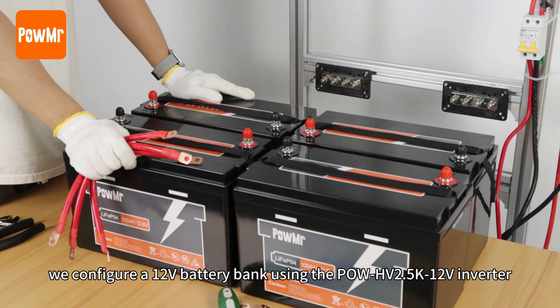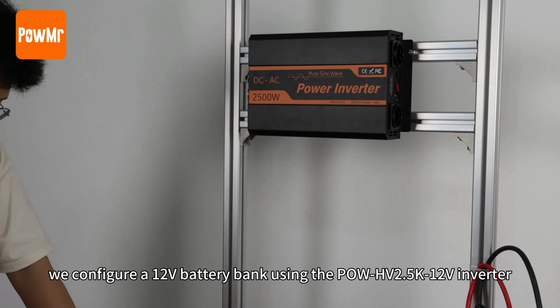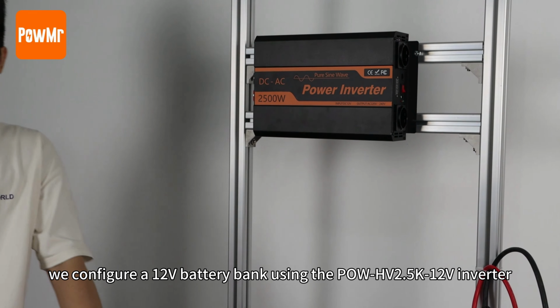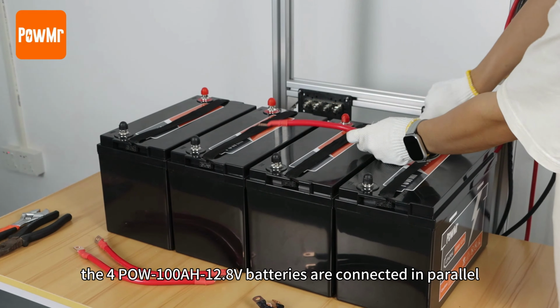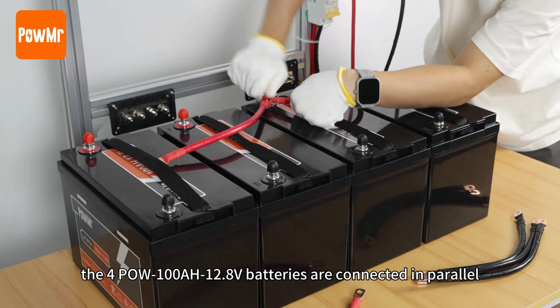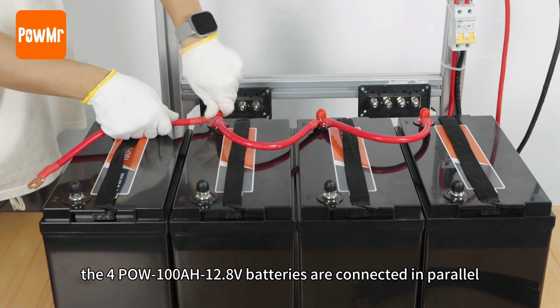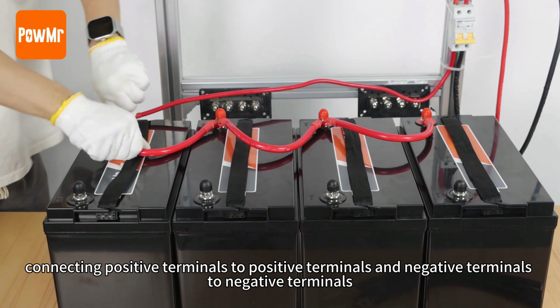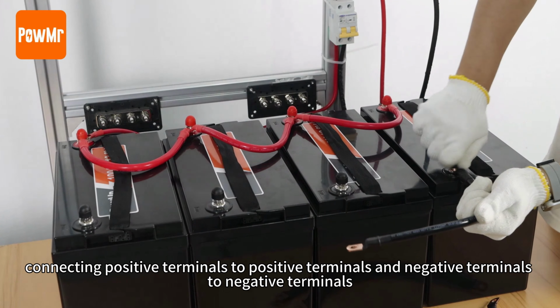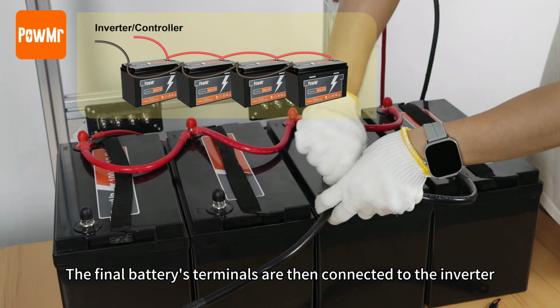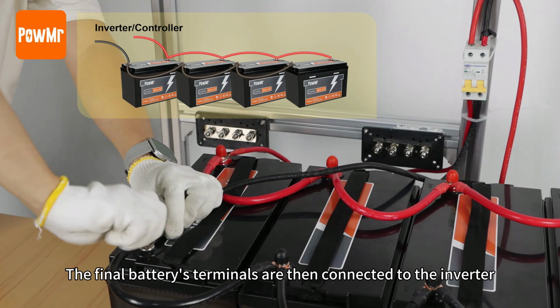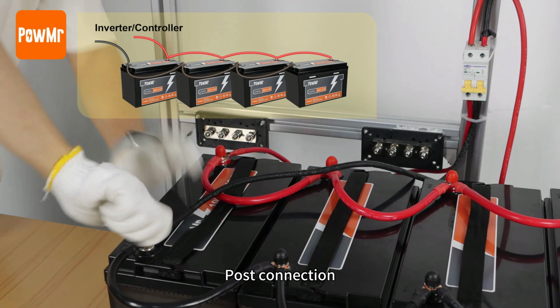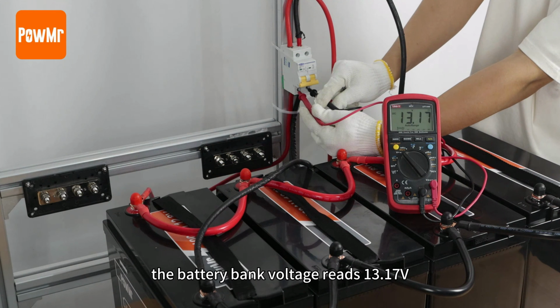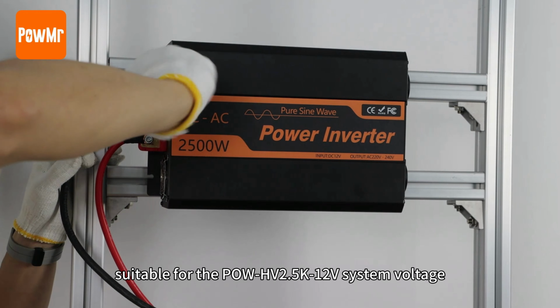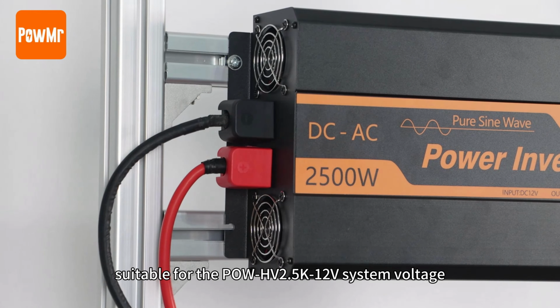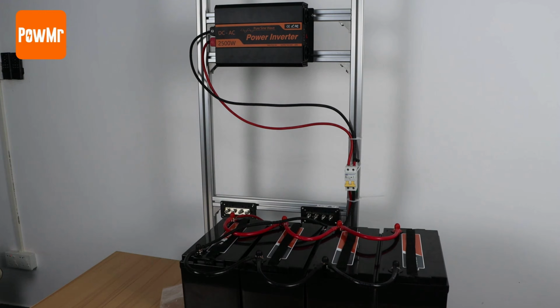Next, we will configure a 12-volt battery bank using the POW-HV2.5K-12V inverter. Here, the 4 POW-100AH-12.8V batteries are connected in parallel, connecting positive terminals to the positive terminals and negative terminals to the negative terminals. The final battery's terminals are then connected to the inverter. Post the connection, the battery bank voltage reaches 13.17 volts, suitable for the POW-HV2.5K-12V system voltage.